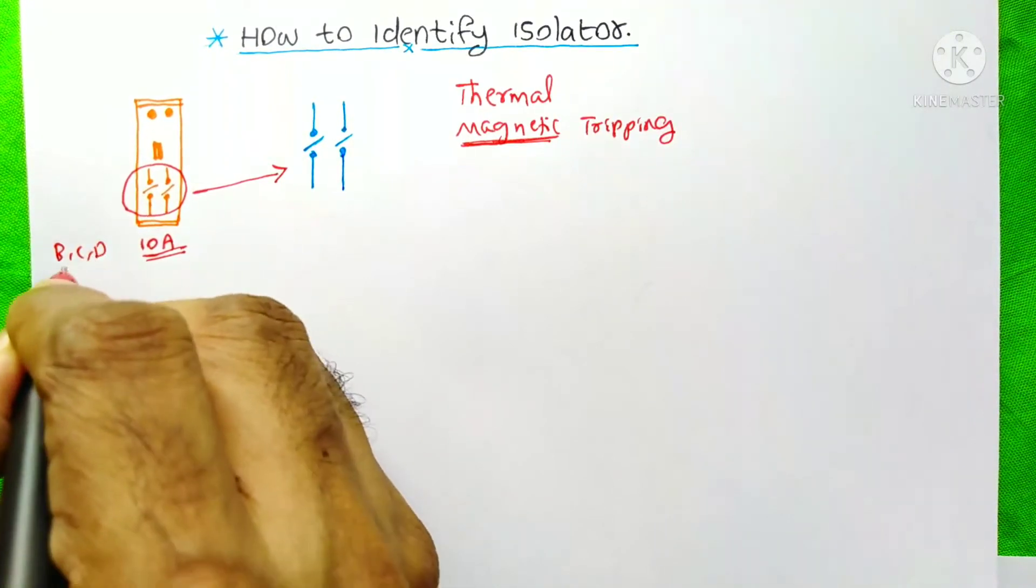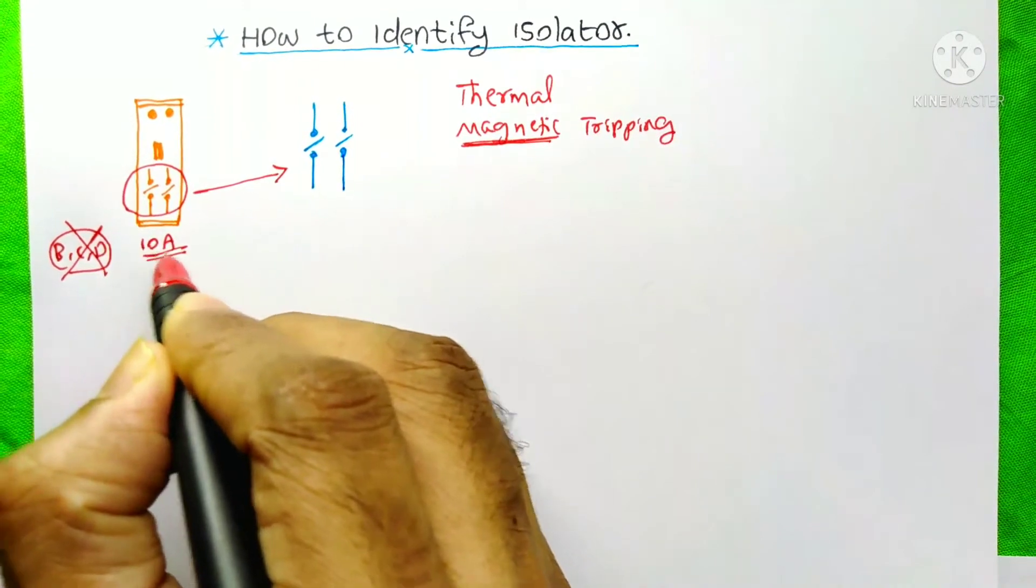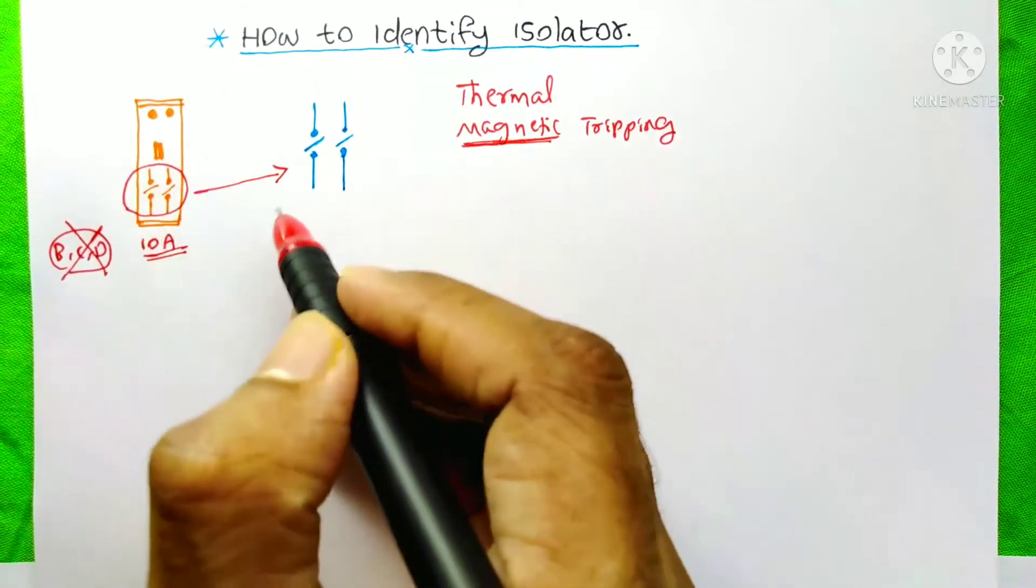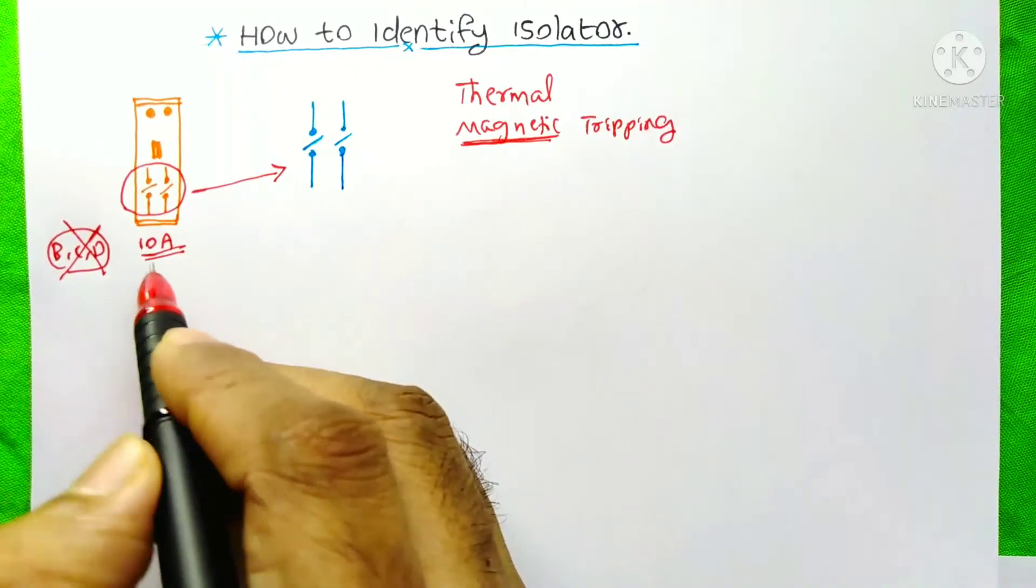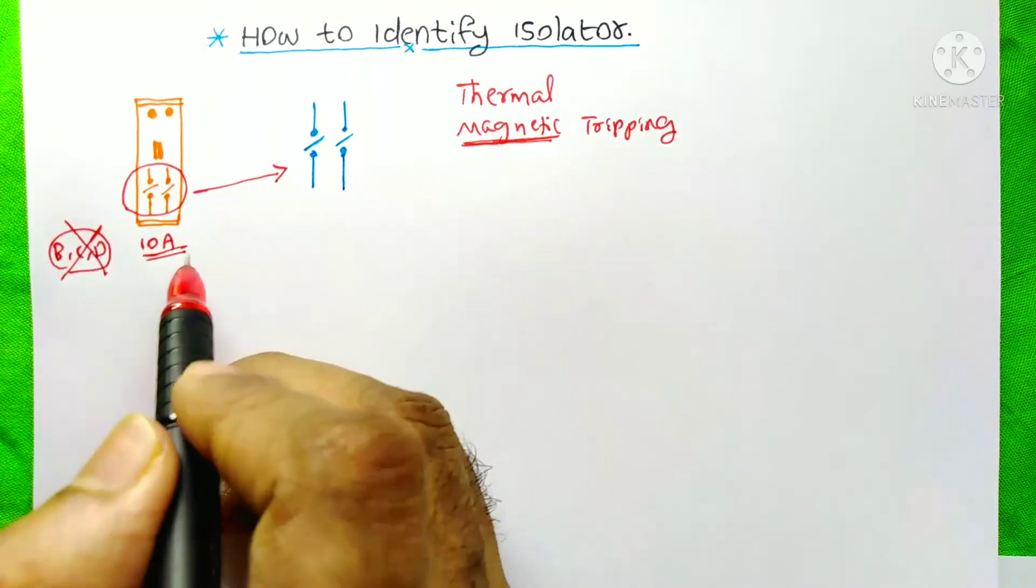You cannot see the B, C or D curves just before this 10A. You can see only this 10A on the top of an isolator. By that you can identify it is an isolator and not an MCB.